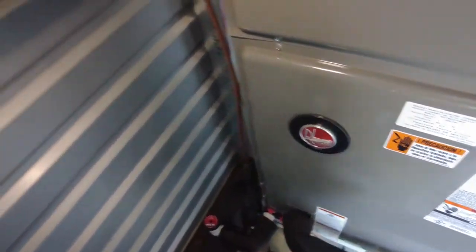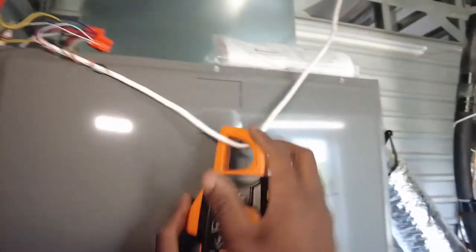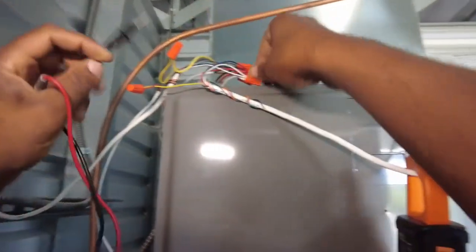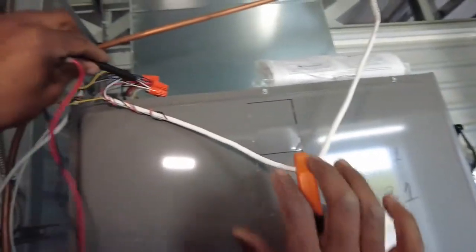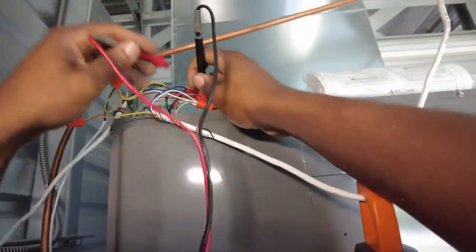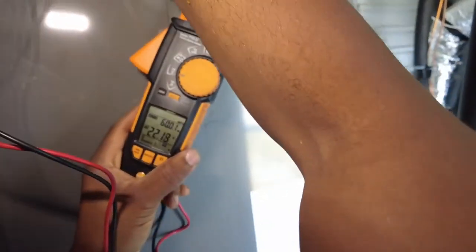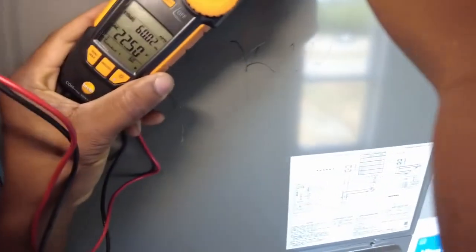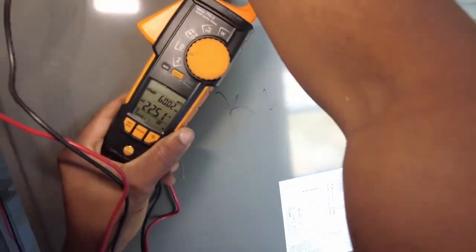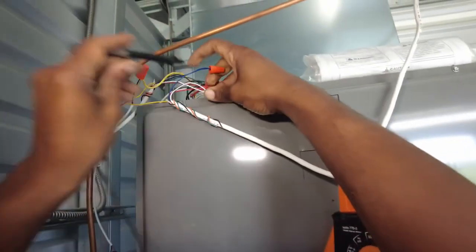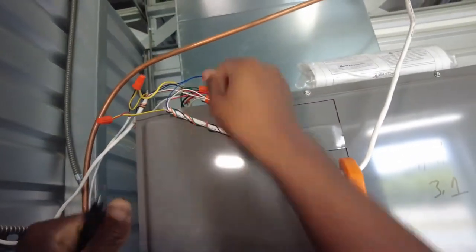Now the unit's kind of short cycling. So just about to check voltage here. See what I've got. Cross my 24 volts and common. As you see, I'm only reading 20, 22 volts, which is very low.